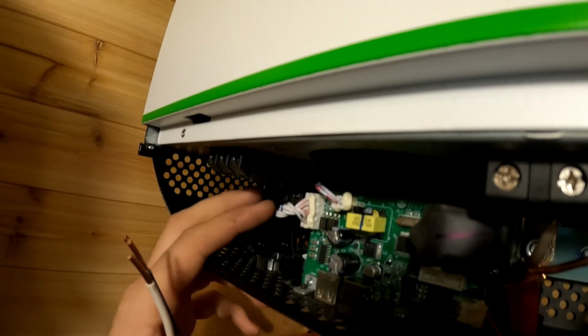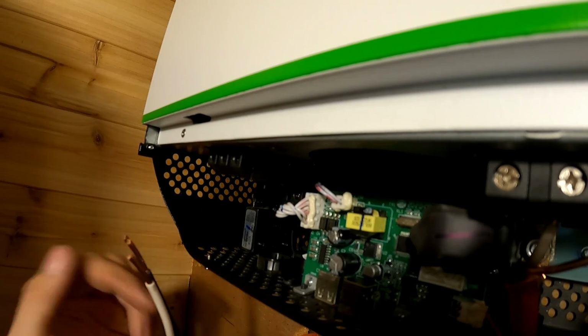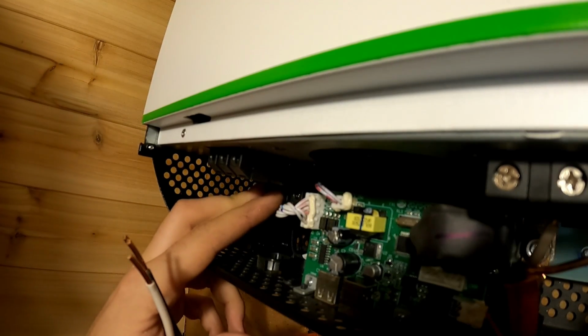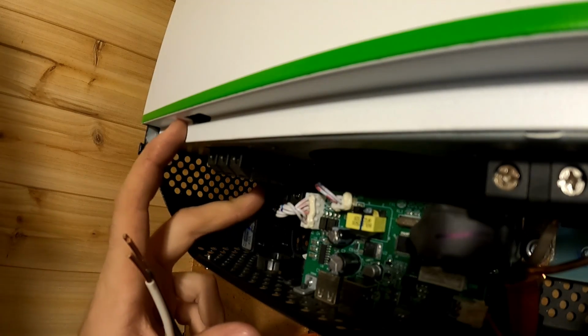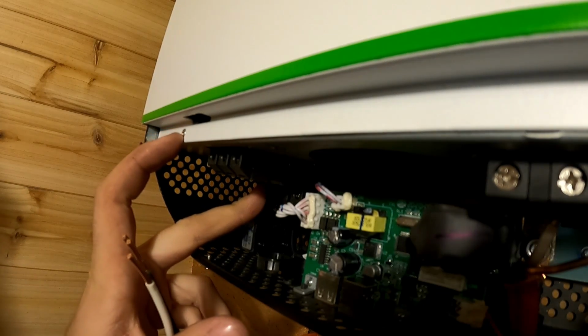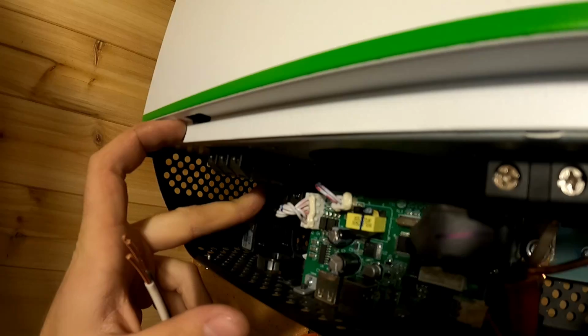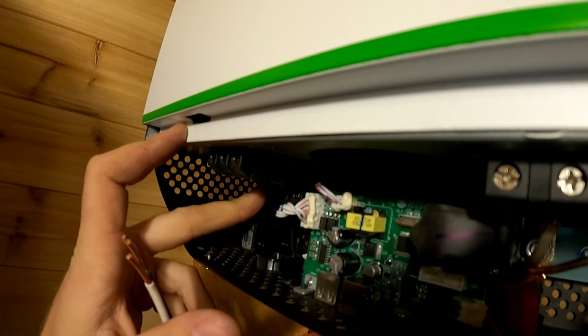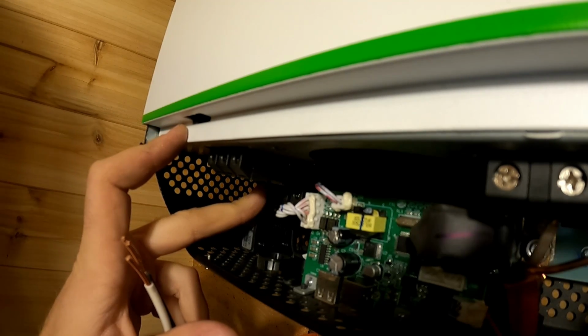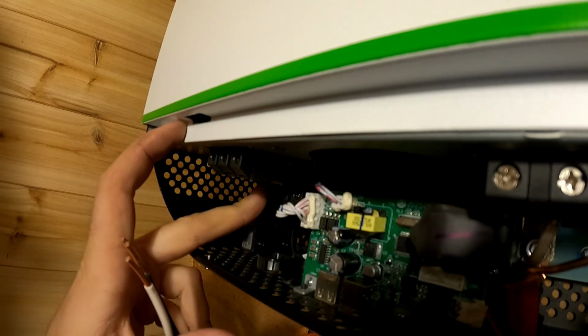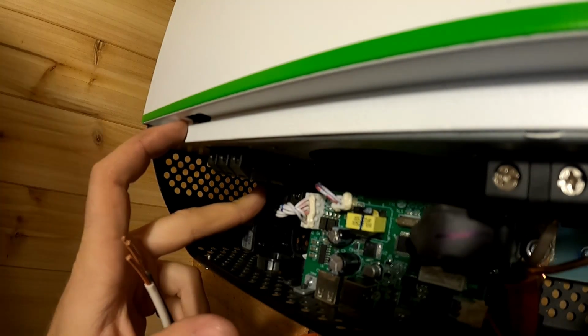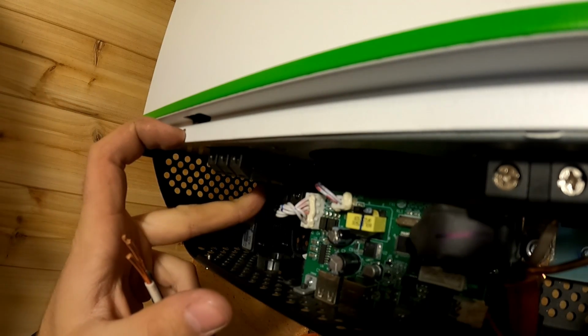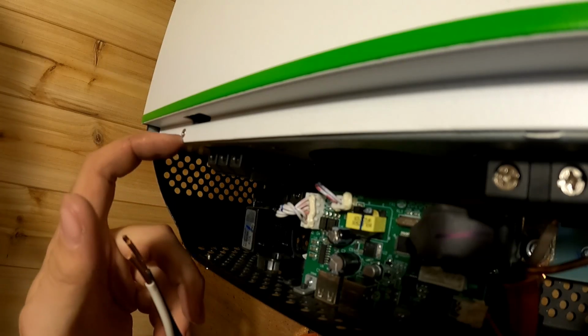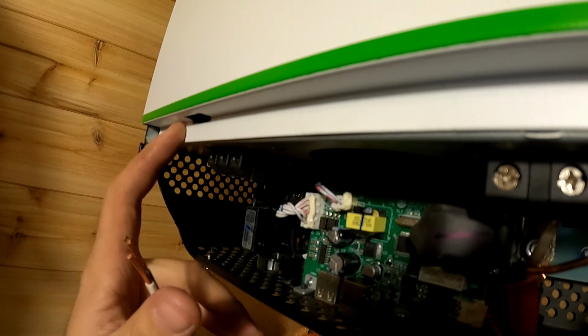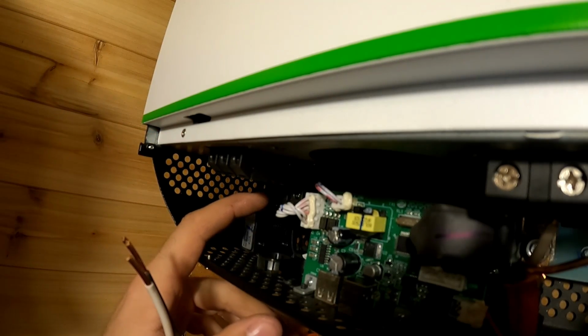So I need to take 10 gauge wires from this, run down to my electrical panel. The inverter here is 30 amps, ish, or 25 amps because it's 3000 with a peak of 6000. But the cool thing with peak currents is you can kind of ignore them. I don't know if you're supposed to, but that's what you can do, and it won't overwhelm the wire if it's just a short period of time. So 10 gauge should be good to run from here to my breakout panel.